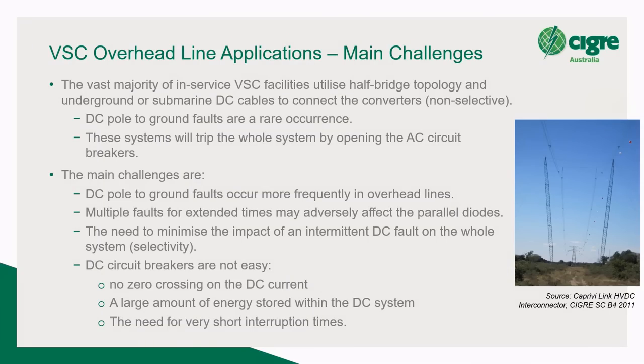So, overhead lines. The vast majority of in-service VSC are using half-bridge converters. The half-bridge topology does not allow you to control the DC current to achieve any kind of zero crossing to allow you to block the converter or restart. Because of this, all but one HVDC VSC system is using underground or submarine cables. There's only one operational right now that actually has an overhead line, and that's the Caprivi link in Africa. I've got a slide on that coming up. But the others use underground and submarine cables.